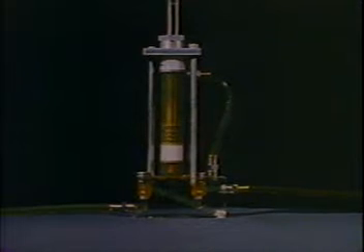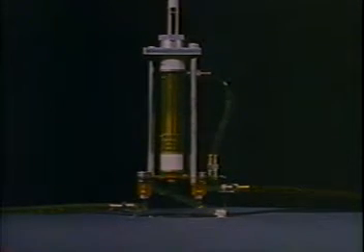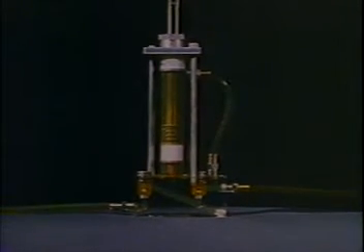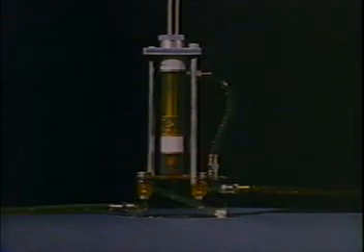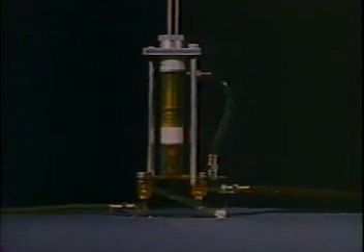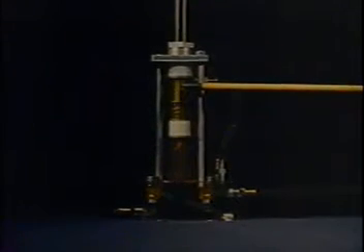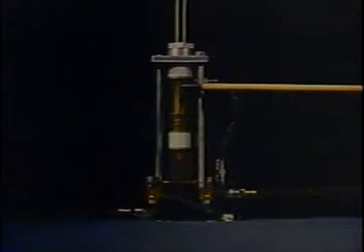The operation of these positive displacement double-acting piston-type pumps, demonstrated with this visible model, shows that the trick to the design which causes it to pump liquid forward on both the upstroke and the downstroke is the establishment of a chamber in the upper half of the pump, which increases in length as the piston moves downward.